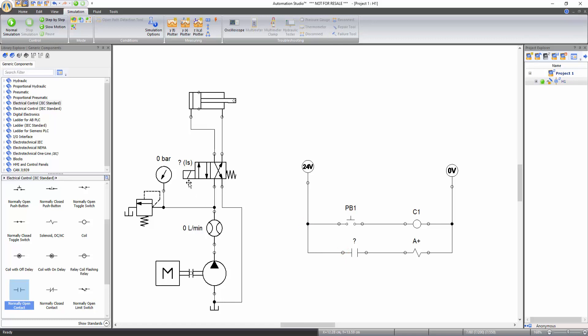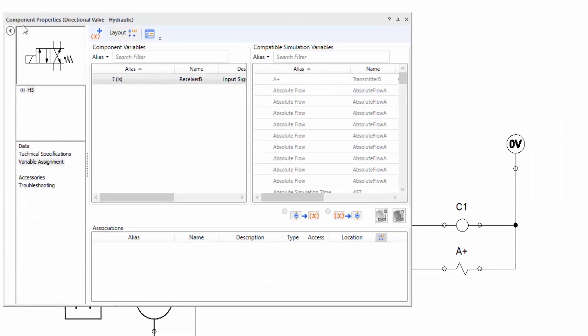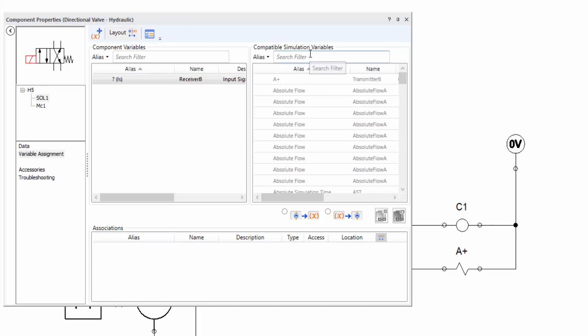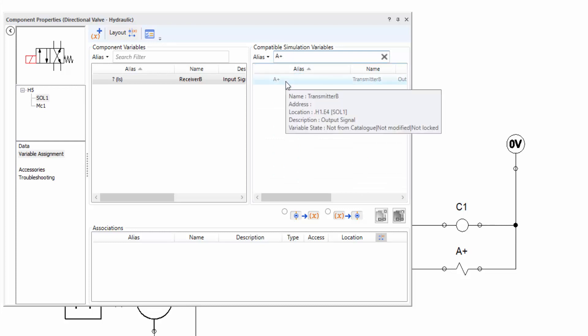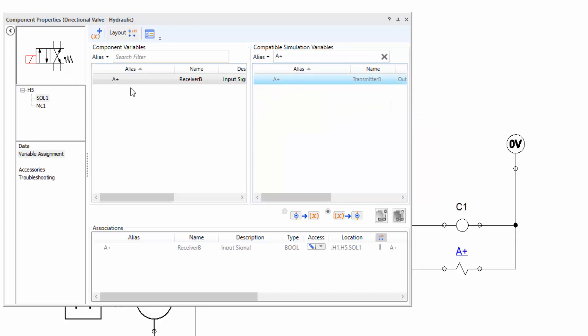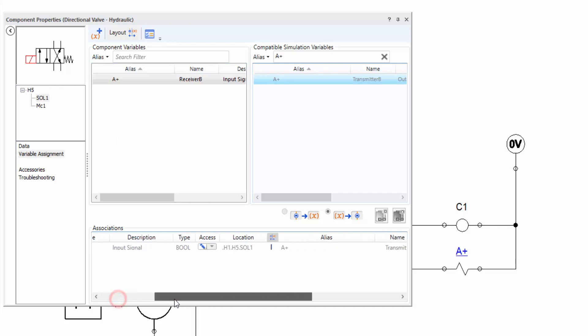Now link the solenoid of the directional valve with the electrical solenoid of the electrical control circuit. Double click on the directional valve to open the component properties window, then click on variable assignment from the left side menu and click on the solenoid icon. Use the filter from the compatible simulation variable section to sort variables — the hydraulic directional valve solenoid must be linked with the solenoid of the electrical control circuit with alias A+. Type A+ in the filter, then double click on the alias to create the link. The question mark symbol is replaced by A+, confirming the link is created.